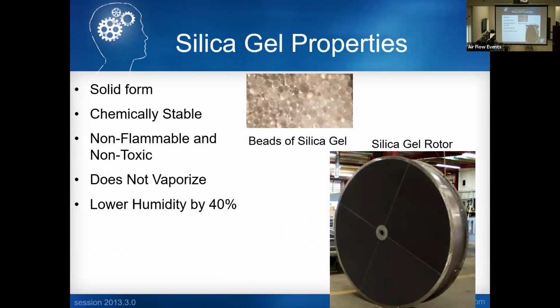Basically, we use silica gel. We use the desiccant rotor. Previously, about 1995 and earlier, we used silica gel beads, which were in a container, and the containers rotated in and out of the process airstream. That technology went aside about the mid-90s with impregnated silica gel desiccant rotors, the dry type rotors. Rotors are non-flammable, non-toxic.